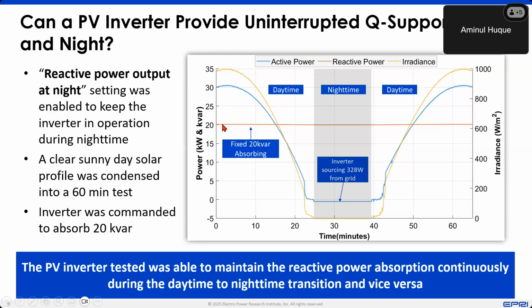But if you follow this orange curve in the middle, the reactive power throughout this period was constant. So it did not interrupt, it did not drop, it just provided that capability. So that's the first answer, that yes, it can do it. Of course, if it offers that capability and if you configure it correctly, it can do that pretty much without any interruption. And what we have seen for this particular inverter is that to do that, it was absorbing roughly 328 watt. And again, it's a 33 kilowatt inverter. We are absorbing 20 kVAR. So the inverter itself was absorbing or importing 320 watt from the grid.